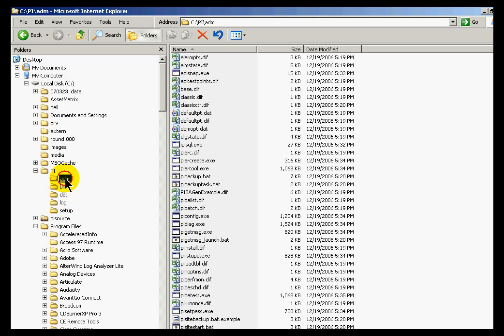Like these interfaces you see right here, that they are started up in the operating system and also in the pisitestart.bat. That does mean you're going to have to edit this pisitestart.bat and put in all those interfaces that are site-specific. And at the same time you're doing that, you should edit pisitestop.bat to make sure that when you stop PI, we stop those interfaces as well.